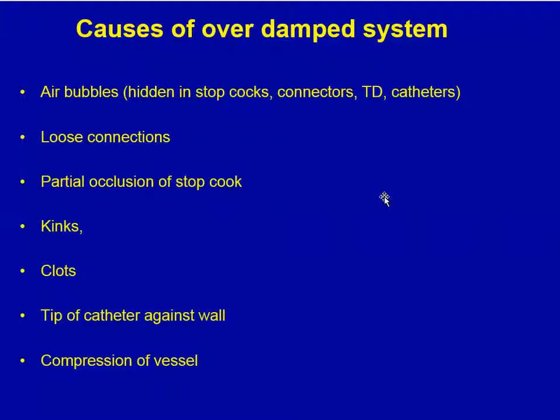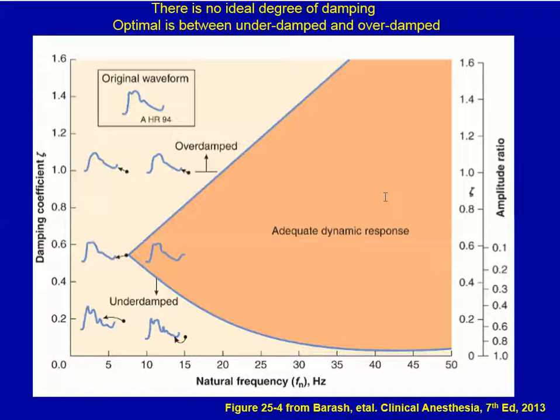Some things that can cause an over-damped system include air bubbles, loose connections, partial occlusion, kinks, clots, the tip of the catheter against the wall, and compression of the vessel.